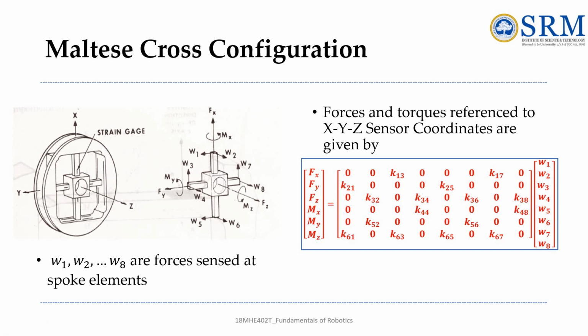Whatever you have seen along the force, you know that 3 and 7 are the Fx. Okay, along the x direction, the forces sensed at the spoke elements are W3 and W7. What is opposite to W3 and W7? What forces sensed at the spoke elements are opposite to this 3 and 7? You have to see, that is W4 and W8. So this will be the torque in the x-axis. Okay, so that is why it is named 4 and 8. That is 4 and 8 are the forces sensed at the spoke elements for strain gauges.